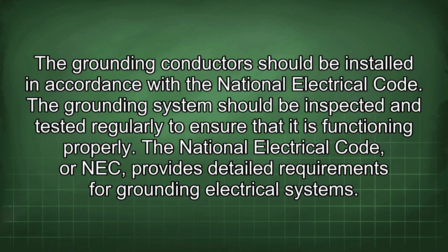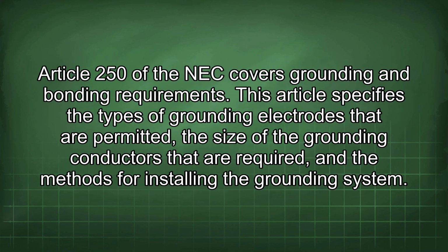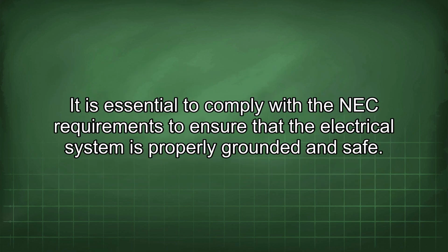The National Electrical Code, or NEC, provides detailed requirements for grounding electrical systems. Article 250 of the NEC covers grounding and bonding requirements. This article specifies the types of grounding electrodes that are permitted, the size of the grounding conductors that are required, and the methods for installing the grounding system. It is essential to comply with the NEC requirements to ensure that the electrical system is properly grounded and safe.